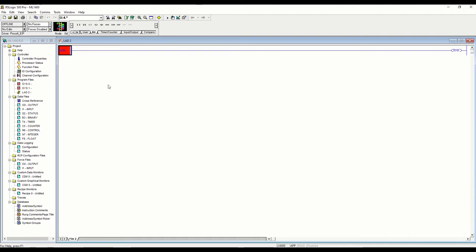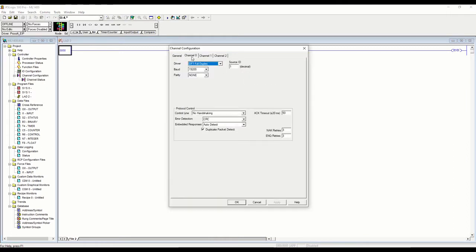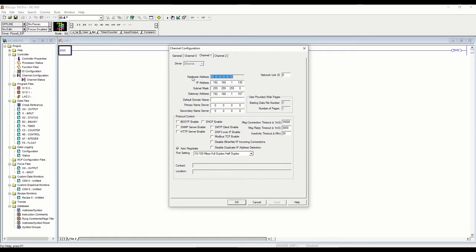First thing we need to do is go to our channel configuration. Channel 0 is our serial port, channel 1 is our ethernet port, and as you can see we already have an IP address configured here — this is a unit I have at my desk. You do have to enable the Modbus TCP, so we're going to check that. You can see that brings up this extra tab, which we'll get to in a second.